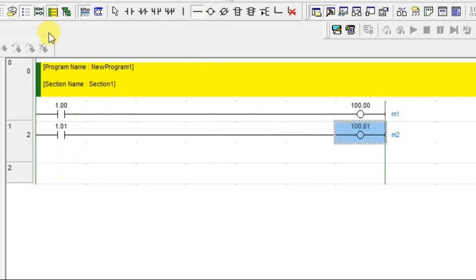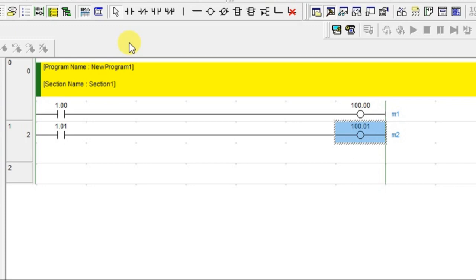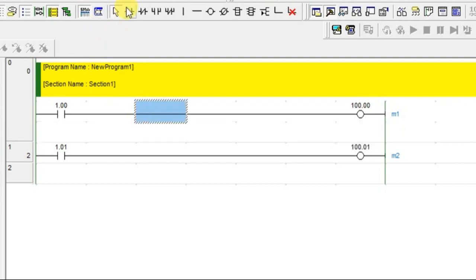My requirement is due to overload, I cannot run both motors at the same time. If M1 is on, M2 should be in off condition. Or if M1 is in on condition, M2 should not be on. Or if M2 is in on condition, M1 should not be on. Like that you can write the interlock using the address of outputs.